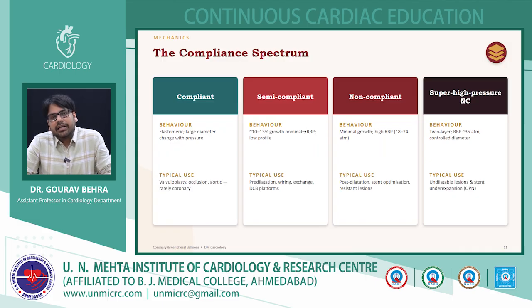The second is the semi-compliant balloon. Semi-compliant means there is a predictable change in the diameter, usually less than 20% growth. So the semi-compliant balloon, we mainly use for pre-dilatation, for exchange, or for these drug coating balloon platforms.